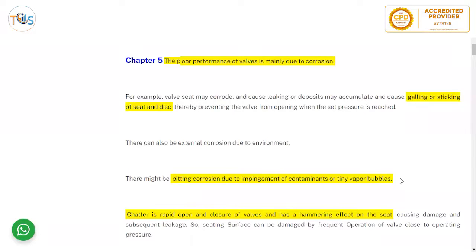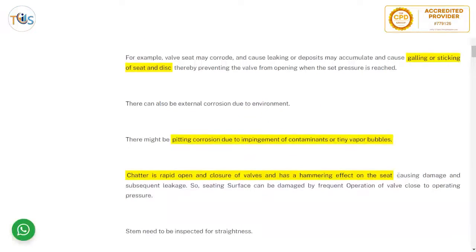The poor performance of a valve is mainly due to corrosion — this is a potential exam question. For example, the valve seat may corrode and cause leaking, or deposits may accumulate and cause galling or sticking of the seat and disc, thereby preventing the valve from opening when the set pressure is reached.